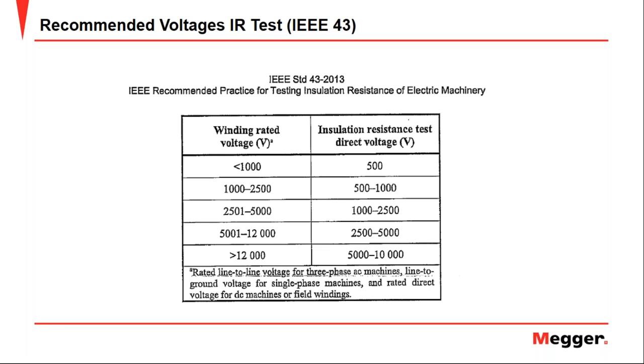There are cases when motor OEMs indicate that the insulation resistance test must be carried out at nameplate voltage. If it is a 4000 volt motor, then the test must be carried out at that voltage and not the one established in the standard. So the message here is that the IEEE 43 standard will never be above the OEM instruction. The recommended values in the standard must be considered when we don't have any type of information or indication from the manufacturer.